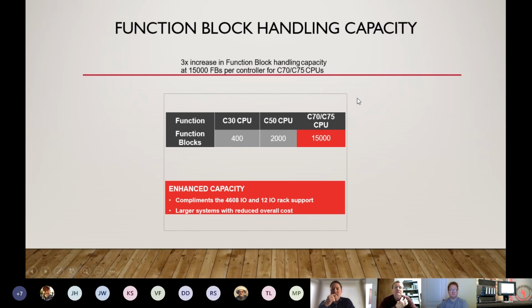On the memory side of the different CPUs that you have, as we're talking about function blocks, it does have a memory capacity for certain function blocks. So a C30, which is kind of the entry-level CPU, you have a function block capacity of 400. The C50, you can program up to 2,000 function blocks. The C70, C75 is 15,000 function blocks.